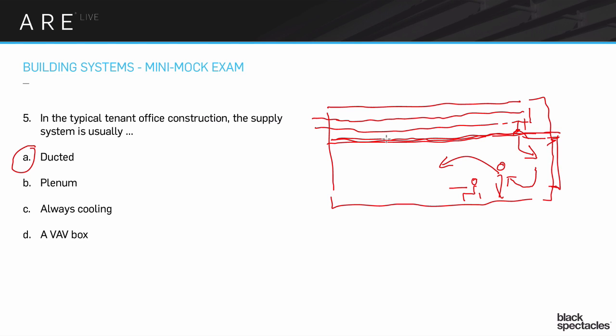And then we're going to put essentially holes into that ceiling. Those holes will probably look very similar to the typical supply vent register. And that hole space up here, the entire interstitial space above the ceiling and below the structural deck, is going to be the plenum area. And that plenum area is going to be attached to a duct that's going to be the return duct. And the supply ducts are going to be attached to those original ducts that we talked about.